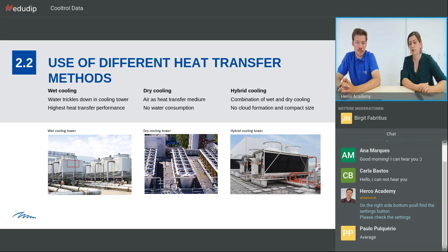And there are also combined forms, lots of different variants really, that are usually all summarized under the topic of hybrid cooling. It's a combination of wet and dry cooling, and the advantage is there is a lot less cloud formation, or almost no cloud formation. In the open cooling tower, of course, there is evaporation, and the water that evaporates is prone to form clouds. So this is the typical cloud you see in the cooling tower of a power plant, let's say, natural draft. Hybrid cooling towers have the advantage that there's a lot less cloud formation, which is good for the microclimate or the people that live next to the plant. And it has also a big advantage, and that's the compact size. It's usually smaller than, let's say, a wet cooling tower.